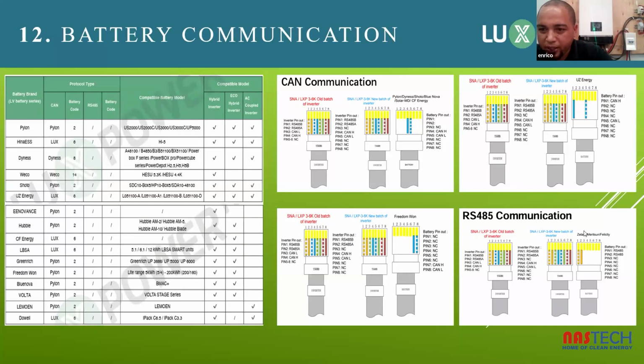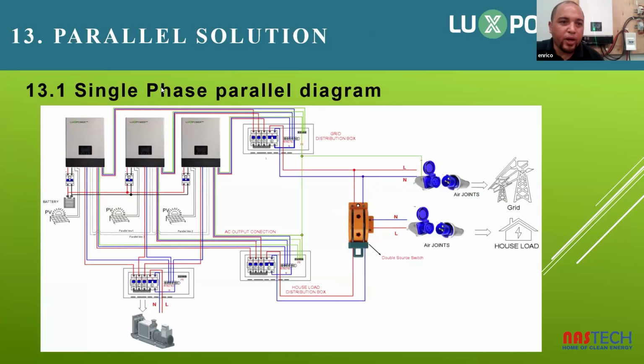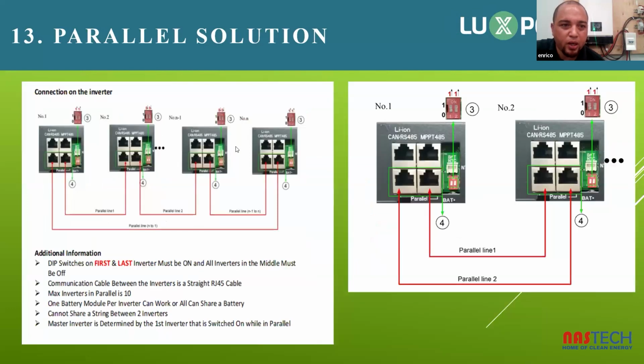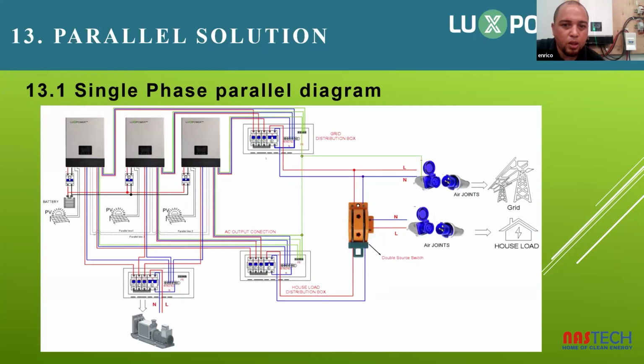These are your cables. The Felicity battery and the Merit Sun use an RS485 communication cable. Parallel, single phase parallel. This is an example. The inverters can parallel up to 16 units. You can do a single phase parallel, meaning all 3 inverters supply one single phase, and you can do 3-phase parallel. I don't have an example of that here. For the 3-phase parallel, we will usually recommend that you put the batteries on a battery bank, for equilibrium in the power that each inverter draws, and as well the battery cable lengths, so that you do not overuse one battery more than the other.